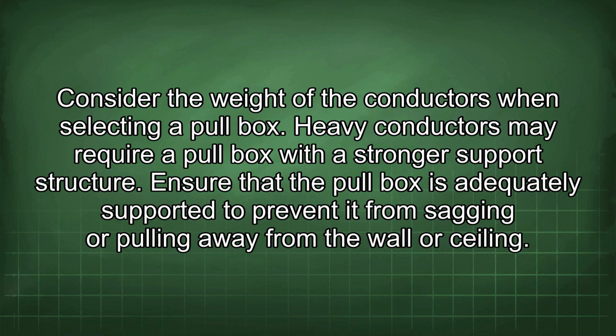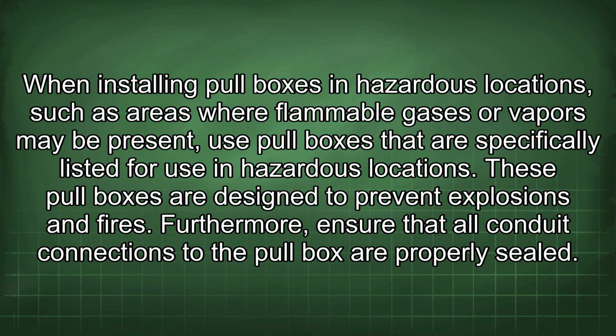Consider the weight of the conductors when selecting a pull box. Heavy conductors may require a pull box with a stronger support structure. Ensure that the pull box is adequately supported to prevent it from sagging or pulling away from the wall or ceiling. When installing pull boxes in hazardous locations, such as areas where flammable gases or vapors may be present, use pull boxes that are specifically listed for use in hazardous locations. These pull boxes are designed to prevent explosions and fires.